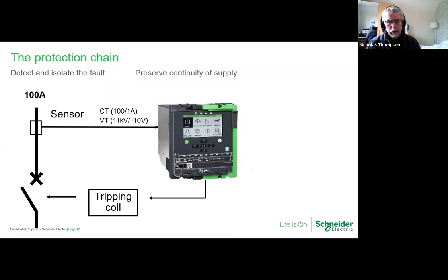With high voltage, you'll find that the protection relay is going to be in its own cabinet or cubicle on top or at the bottom of the switchgear. On the really high voltages like the national grid, they will have a room dedicated for protection relays, and all the information is coming in from the circuit breakers, and these circuit breakers are huge. You're talking tens of meters tall in some cases on the really high voltages, and it's not a room that you would want to be in if it trips. So anyway, let's work through how the whole thing works.